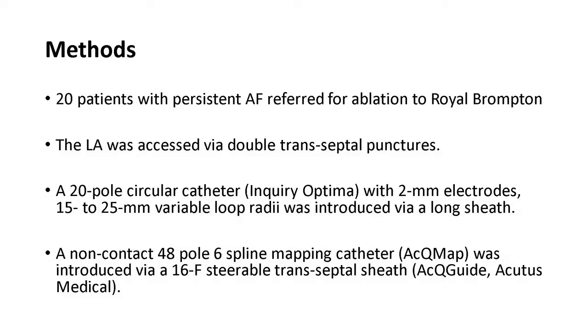A 20-pole circular catheter, an Inquiry Optima with 2 mm electrodes and 15 to 25 millimeter variable loop radius, was introduced via a standard long sheath, and the non-contact catheter, which you've seen on the previous slides, the AcQMap, was introduced via a 16 French steerable transseptal sheath known as an AcQGuide.